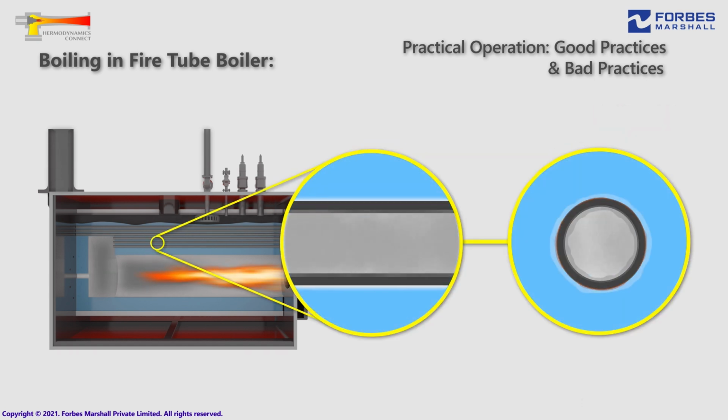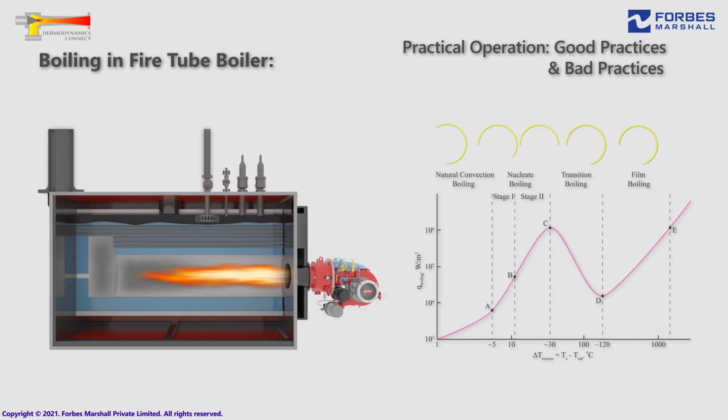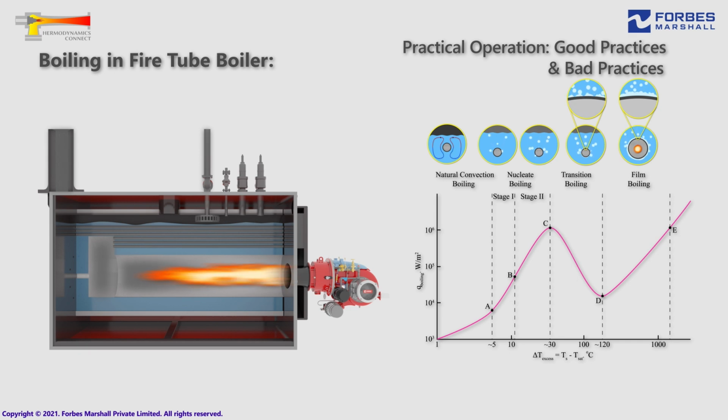Due to increased thermal resistance, higher temperature difference is needed to transfer the same amount of heat. The steam requirement from a boiler is dependent on the requirement of the process plant. This means combustion of more fuel to achieve the same steam generation. This reduces boiler efficiency. Due to exposure to higher temperatures in the boiler, the corrosion effects are accelerated. This reduces the overall life of the boiler. The higher temperatures also mean that the well-placed boiling regimes that we saw are also disturbed.